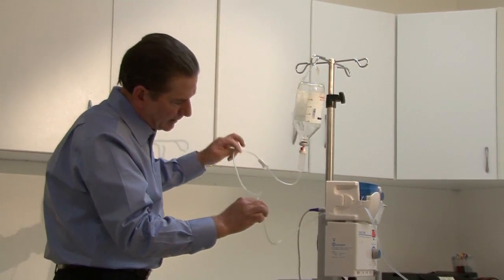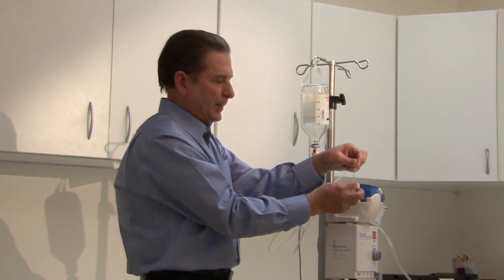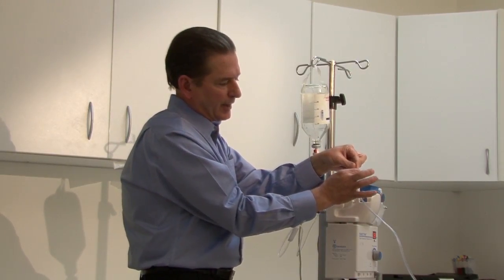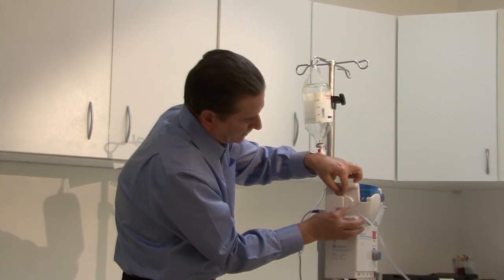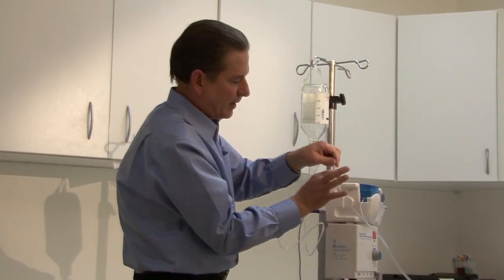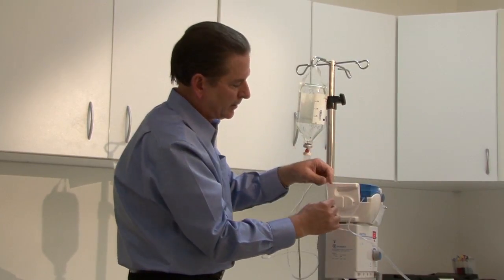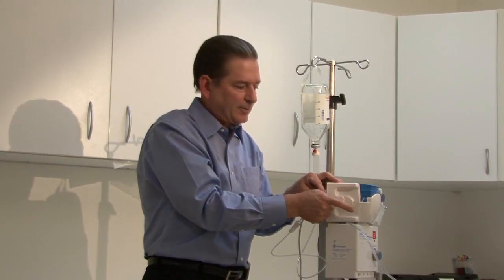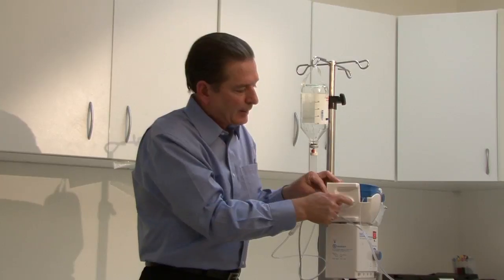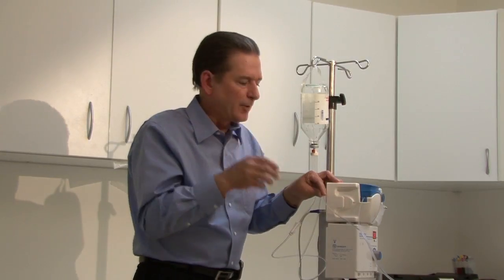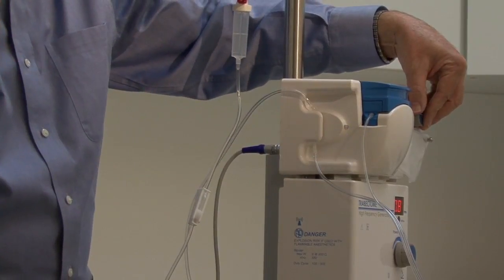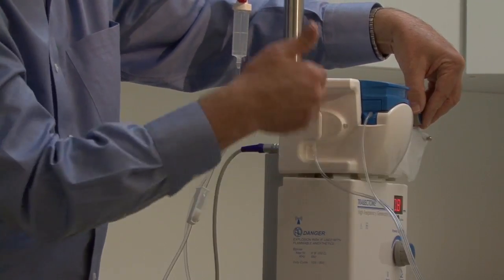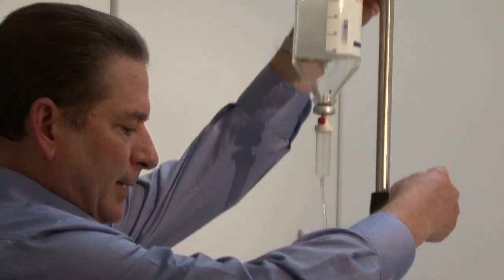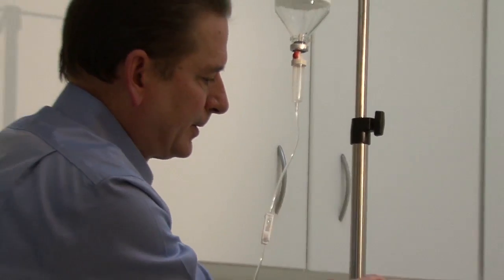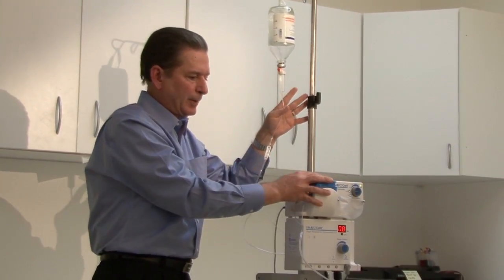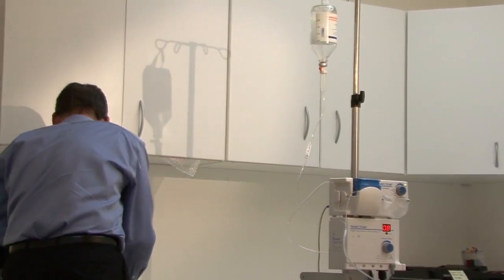So if we start with the bottle spike and go down the tubing set, you'll see that we'll get to this little piece of soft, stretchy tubing. This is where we're going to turn the irrigation on and off. And that's going to happen right here in this little slot. That's where a little pinch valve pinches this tubing open and closed to turn the irrigation on and off. Now, when this light is off, that means the irrigation is off. When this little blue light's on, the irrigation is flowing, meaning it's open, and you'll see that little tubing being pinched open and closed to turn on and off the irrigation flow from the bottle. So that completes the setup of the pump tubing. Now, while the circulator is setting up the pump, whoever's scrubbed in can go ahead and be preparing the handpiece.